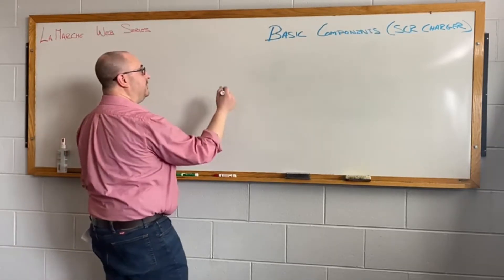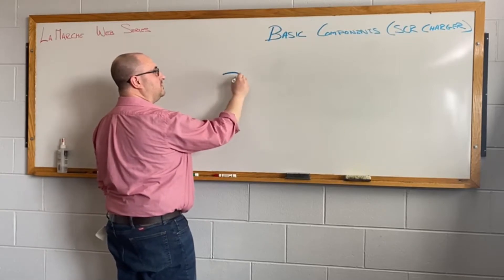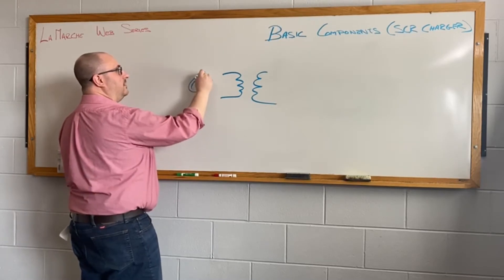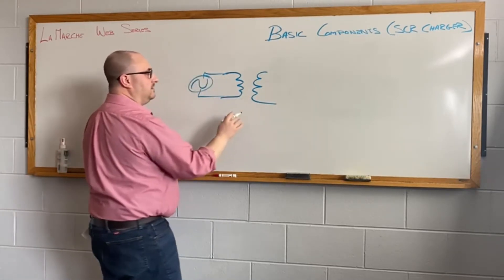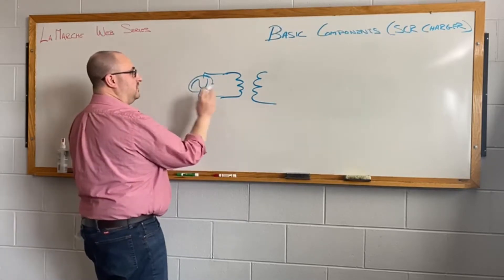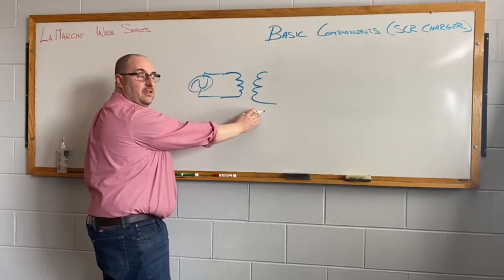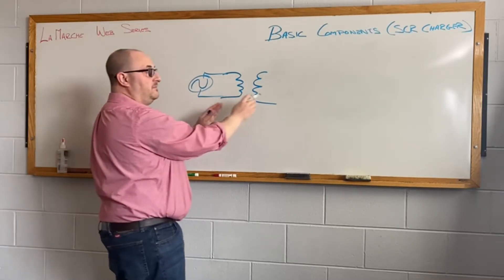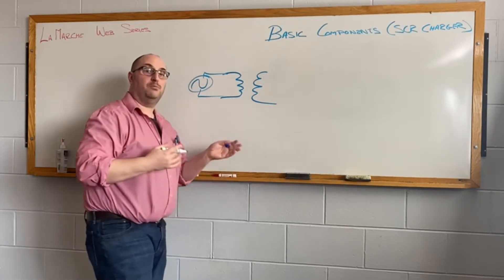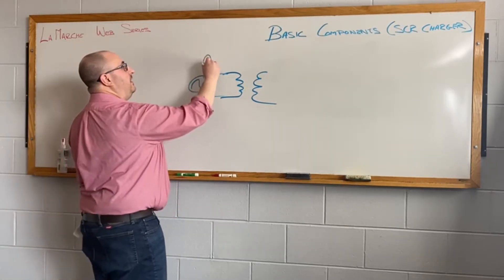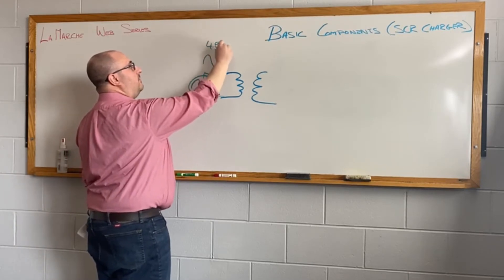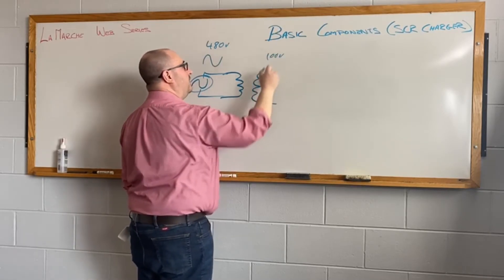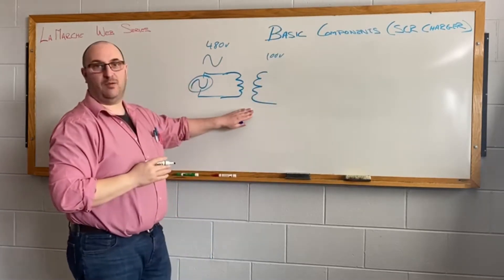Any SCR type battery charger in this market space is going to start out with a simple power transformer that we're going to connect an AC input voltage to. The job of the transformer is going to be to provide isolation from the primary to the secondary side and also to adjust the voltage of the primary down to the secondary voltage that we need for your particular battery size. You may have an AC voltage here that's 480 volts where you might need to step it down to, say, 100 volts. That's the job of the transformer.